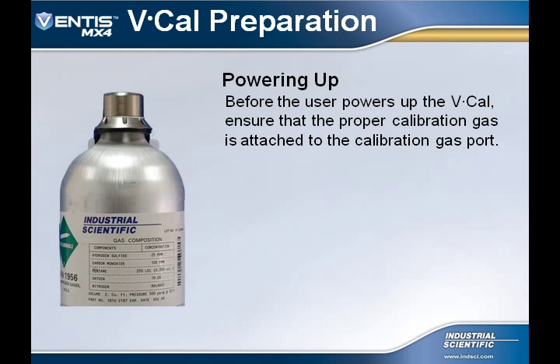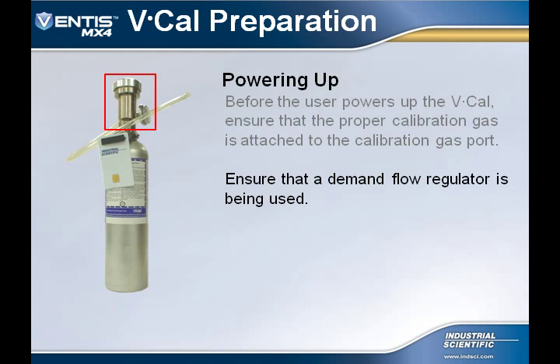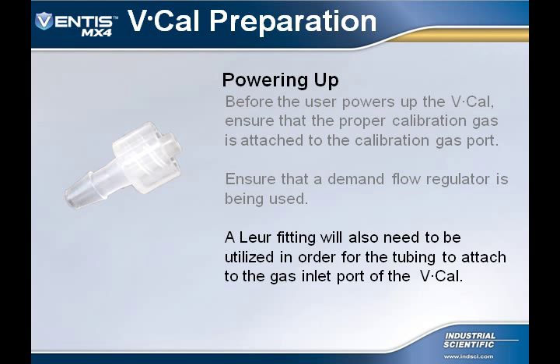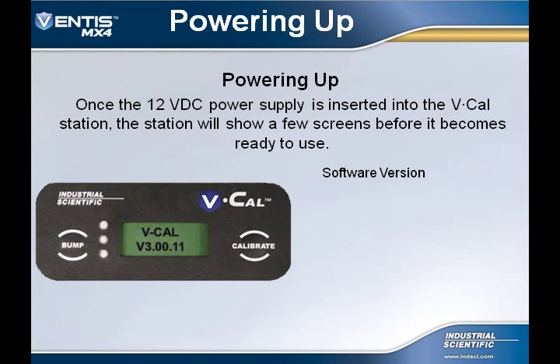To prepare your VCal for powering up, ensure the proper calibration gas is connected to the calibration gas port. The VCal requires the use of a demand flow regulator connected to the calibration gas bottle. A luer fitting will be needed to attach the calibration gas to the calibration inlet port. Once powering the VCal for use, the VCal will cycle through a few screens before it's ready to use.